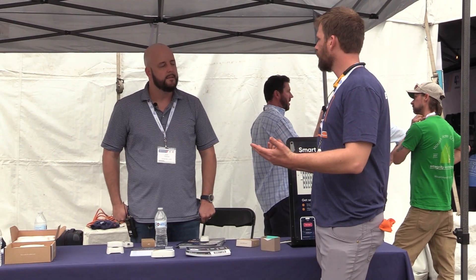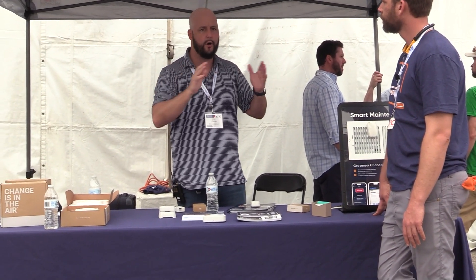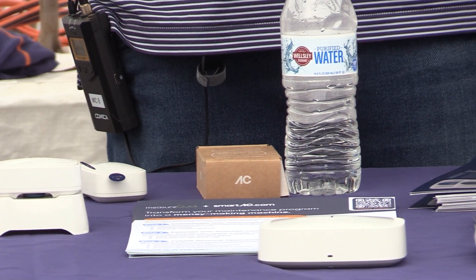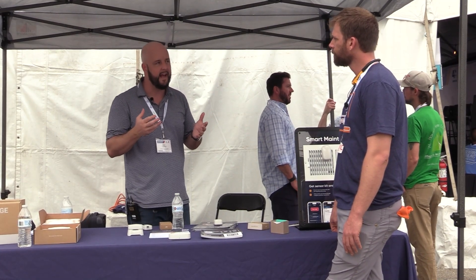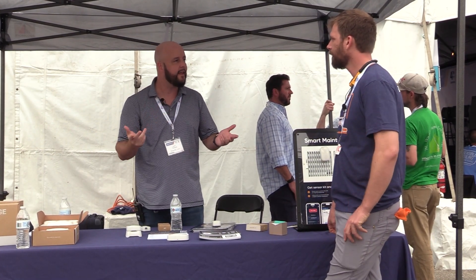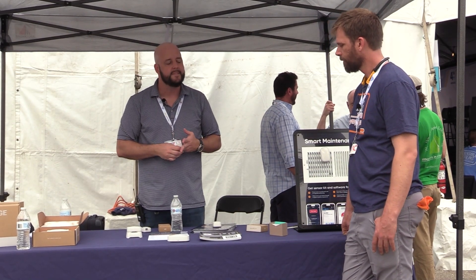The homeowner has an app where they can see high-level info — filter status, water leaks, things like that. The partner dashboard gives everything in detail — you can dive into the metrics of every single cycle all year long. Usually you geek out for a few weeks and then you just live in the leads area. A lead pops to the top, you click on it, look at the data — the split is down eight degrees, different from last week. Maybe you snooze it for a day, come back, it's still bad, so you call Miss Jones. She can look at it in her app and say, 'Come on out.' Eliminating unnecessary truck rolls is a big deal.